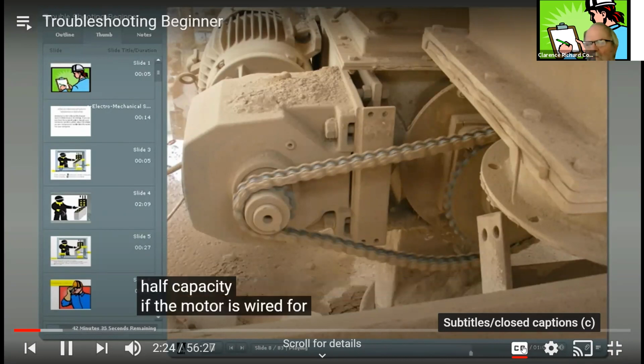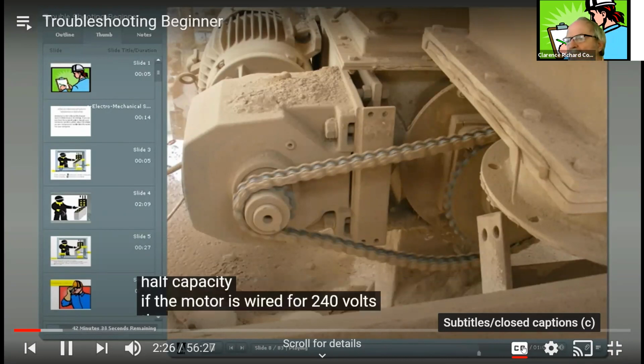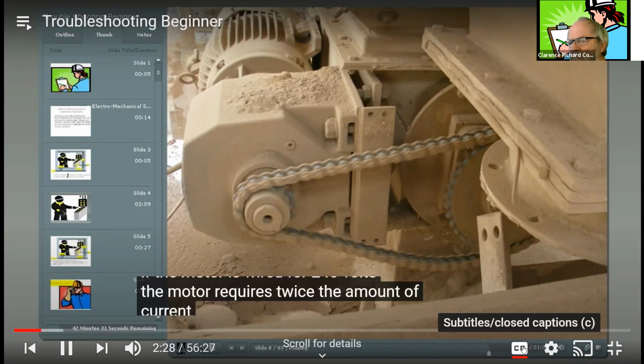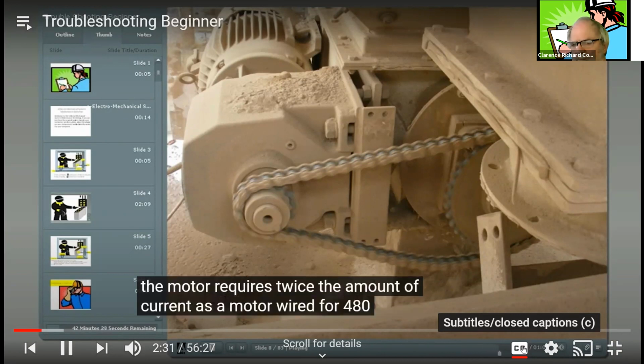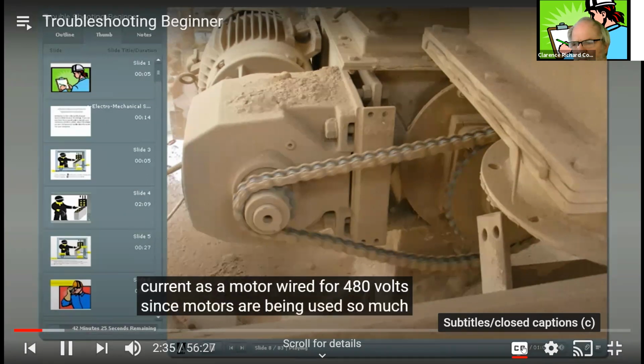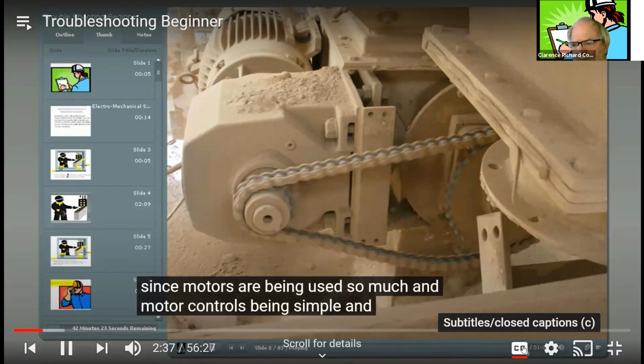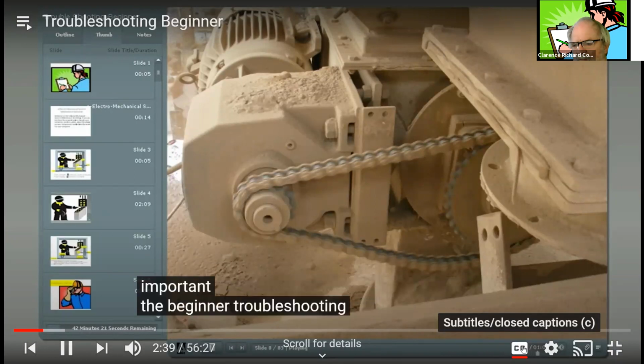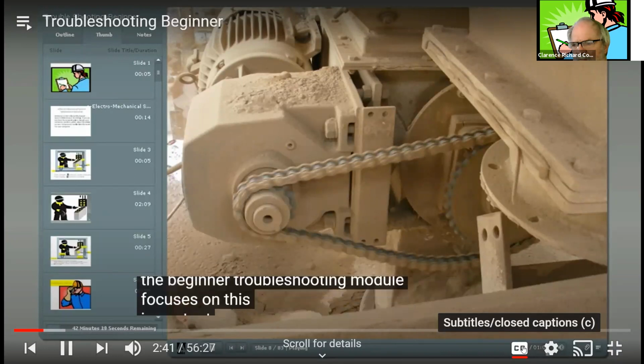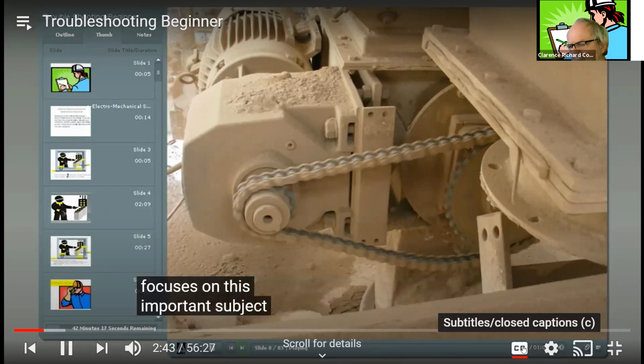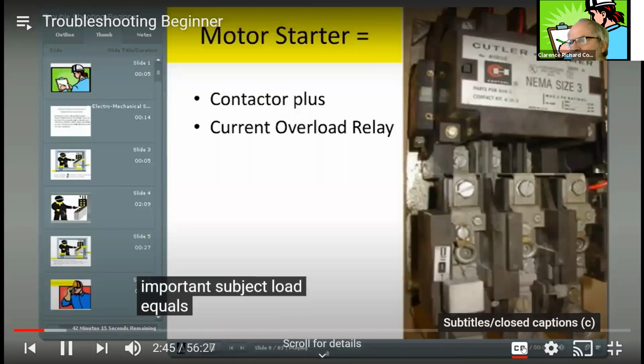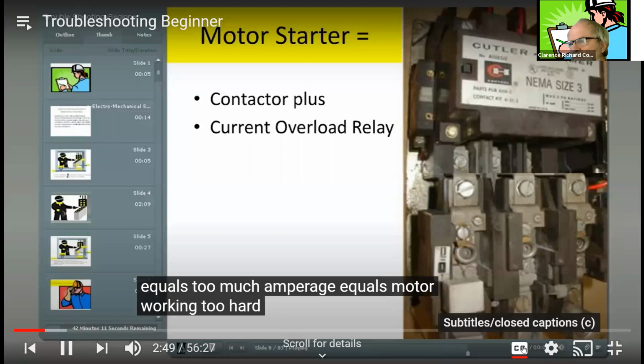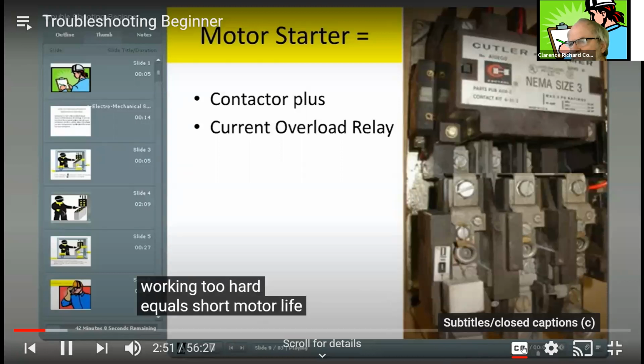If the motor is wired for 240 volts, the motor requires twice the amount of current as a motor wired for 480 volts. Since motors are being used so much, and motor controls being simple and important, the beginner troubleshooting module focuses on this important subject. Load equals too much amperage equals motor working too hard equals short motor life expectancy.